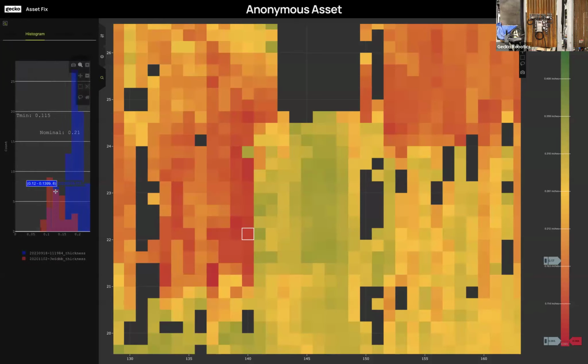We could look at a histogram of the data. What's the breakdown of all of these readings by thickness? So this blue curve here is the recent inspection that we did. And it's showing, hey, you've got a lot of readings that are in a reasonable range, and a fair number of them are getting pretty thin. It's that right side that we saw. We're also seeing another histogram from a previous inspection. So here on this 3-inch section of tube, we've got maybe 50 readings from 2020.